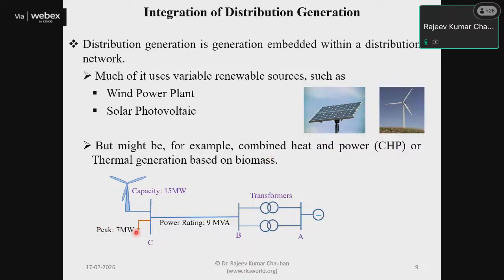Let's consider the example shown in the figure. We have a grid connection, which connects to a particular local site through two transformers, and then we have connections with a wind power plant and the load. Here we have a load of a particular industry with a peak load capacity of 7 megawatts, and the capacity of the wind power plant is 15 megawatts. The line capacity is 9 MVA.